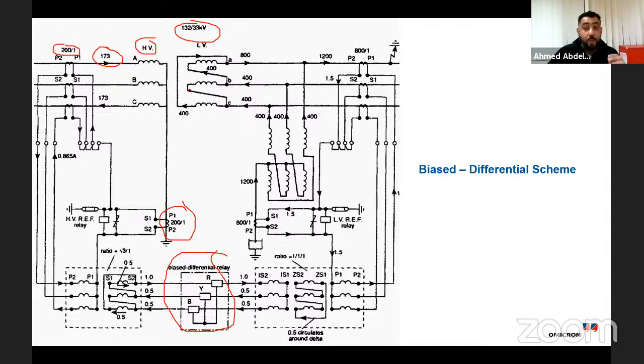All of us know the importance of directionality in differential protection, because we said differential protection depends on directionality. The current in will be positive and the current out will be negative. So if I use a wrong directionality terminology, at the end I will see the current swapped in the wrong direction, and the relay might operate in case of an external fault and not operate in case of an internal fault. So I need to define where P1 and P2 are. And from the CT itself, I can say that we have two types of directionality, or rather polarity. The correct word is polarity.